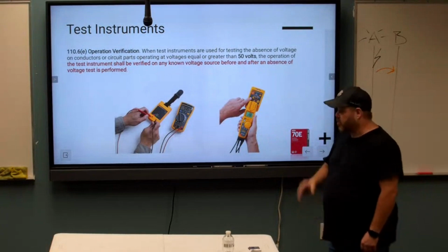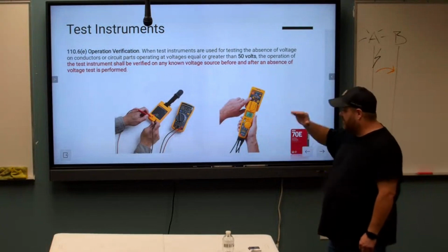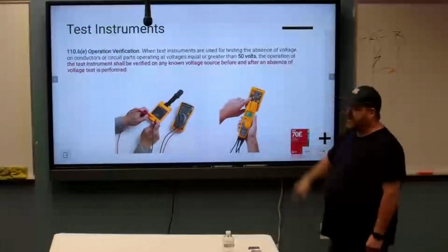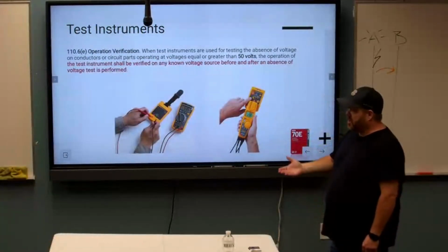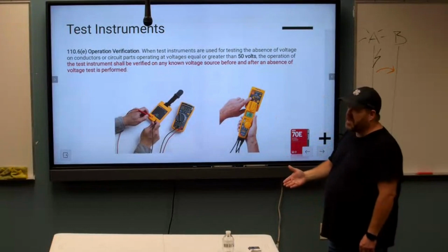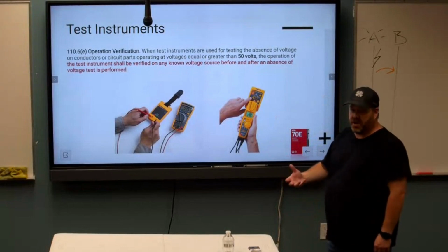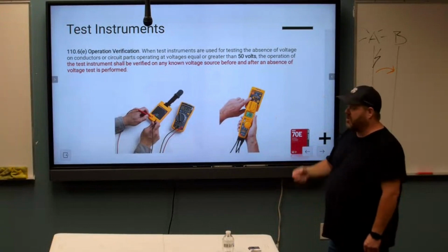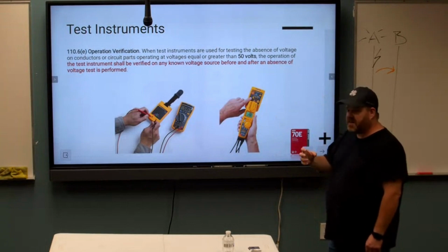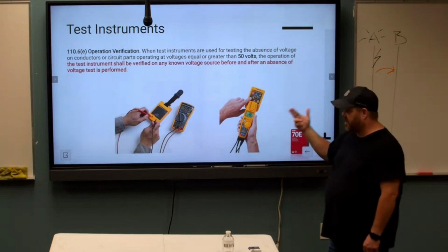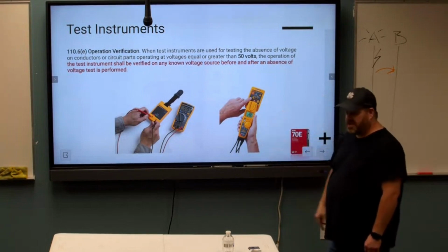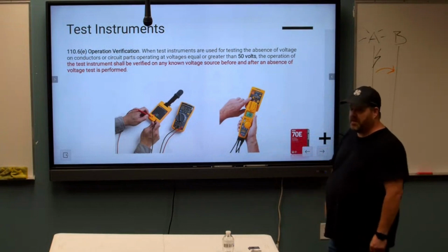Now the categories are really important. If you're not using at least a category 3 or category 4, you're not going to be protected. Sometimes things called transient voltages or spikes occur—if there's lightning outside, or the power company is switching for just a fraction of a second, hundreds of thousands of volts could go through that circuit and blow that meter up, causing a gigantic arc flash explosion right in the palm of your hand.